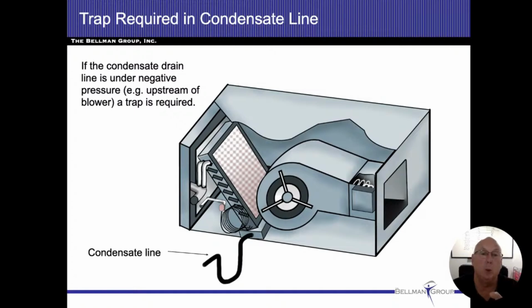Because the air conditioning coil is going to be under a negative pressure, that also has to have a trap in it. If I don't have something that's going to stop the air from coming back in there, then the water is going to have trouble getting into it just to drain in the first spot. The air is going to keep it backing up into the pan. But once I got that trap in there, then the water's going to flow and it'll just get past it just fine. It won't be an issue.